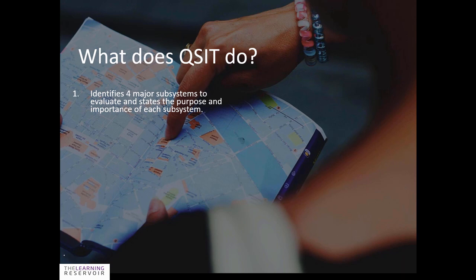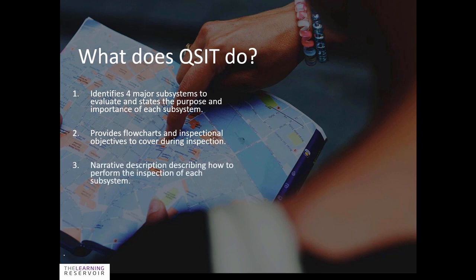What does QSIT do? Well, it's a guide for the inspector. In this slide here we can see the map — it's giving inspectors a guide on how to do an inspection of the quality system of a medical device company. It identifies four major subsystems to evaluate and states the purpose and importance of each subsystem. It provides flowcharts within the QSIT document and inspectional objectives to cover during the inspection. It provides narrative descriptions describing how to perform the inspection of each subsystem, and it provides tables for statistical sampling of records for review. All of that is in the QSIT.